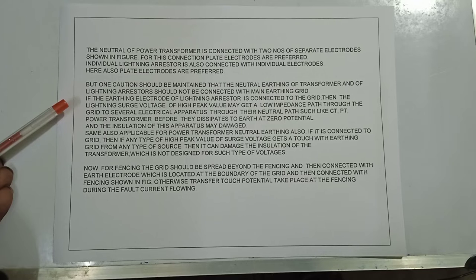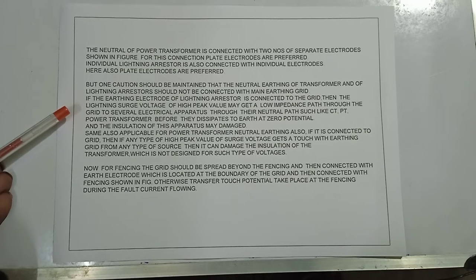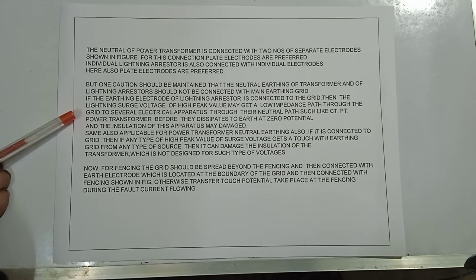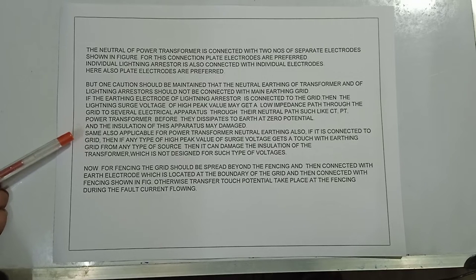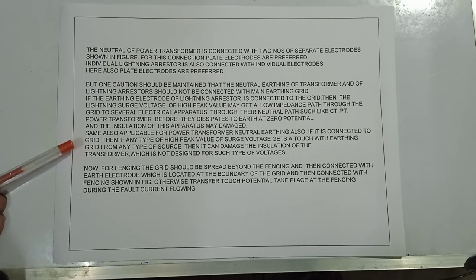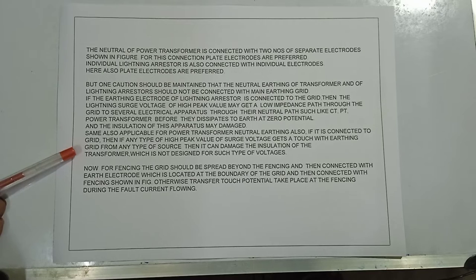If the earthing electrode of the lightning arrestor is connected to the grid, then the lightning surge voltage of high peak value may get a low impedance path through the grid to the neutral path of equipment such as CTs, PTs, and power transformers before dissipating to earth, and the insulation of these apparatus may be damaged. Similarly, if the power transformer neutral is connected to the grid and any high peak voltage reaches the grid from any source, it can damage the transformer insulation, which is not designed for such voltages.